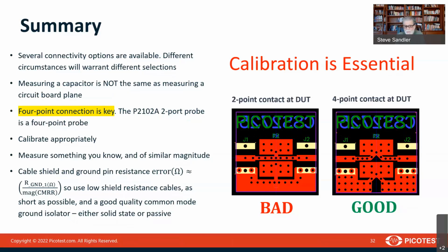My biggest tip is always measure something you know and make sure that it's of a similar magnitude that you want to measure. So, for example, when Mayo Clinic needed to measure 32 microhms, we could measure a milliohm and say, okay, so we now got a valid setup, and then measure the 30 microhms. But those aren't the same magnitude. So that doesn't prove that we can accurately measure 30 microhms. It would only prove that we could accurately measure 30 milliohms.